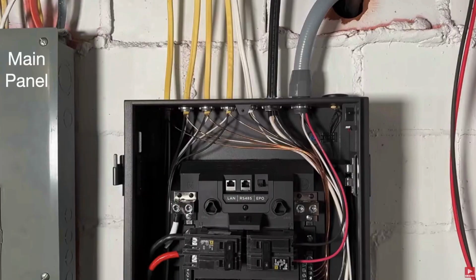We have already seen, in a previous video, that a subpanel could be the means by which standby power is supplied to a home. This slide shows an actual installation of a smart home panel 2, that has both the generator input, as well as connection to the main grid panel. You can see the circuits that need to be secure entering the panel at the top and are tied to the individual breakers inside this panel. Installers have drilled holes to connect the NMD cables for 1 to 12 load circuits.